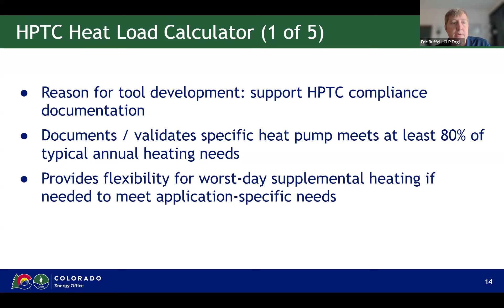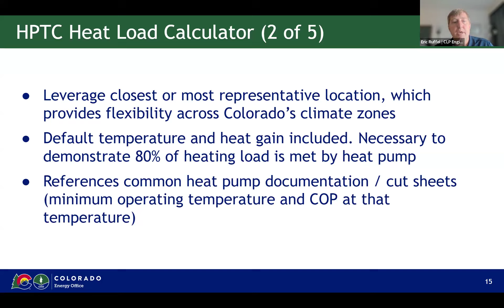In using this tool, it's important to select the closest or most representative location. Across Colorado, we have quite a few different varieties of local conditions and weather, so the tool has been adapted to recognize that variability. The tool references common cut sheet or manufacturer data and uses that as an input. Key documentation to compile includes the manufacturer's minimum operating temperature and the coefficient of performance, or COP, at that temperature. COP is fundamentally an efficiency metric. If you have a COP of 2, 2 units of heat energy are being brought from outside the building into the building for each unit of electric energy input into the heat pump. As another point of comparison, a resistance electric heater has a COP of 1.